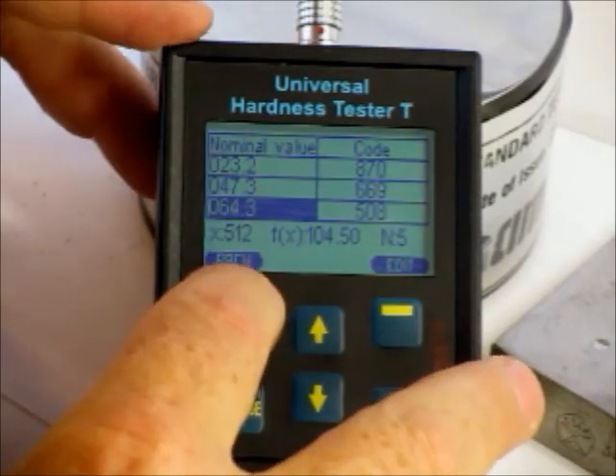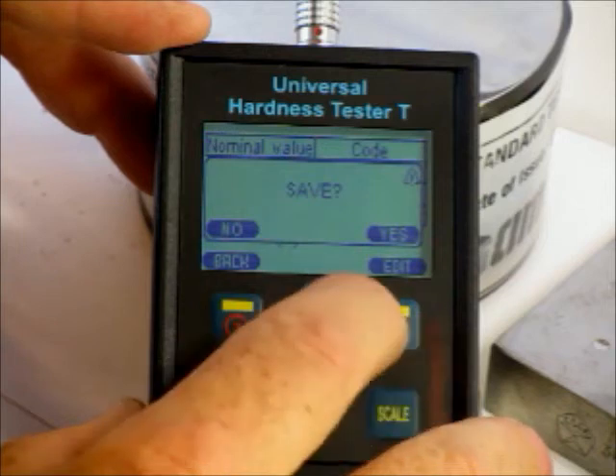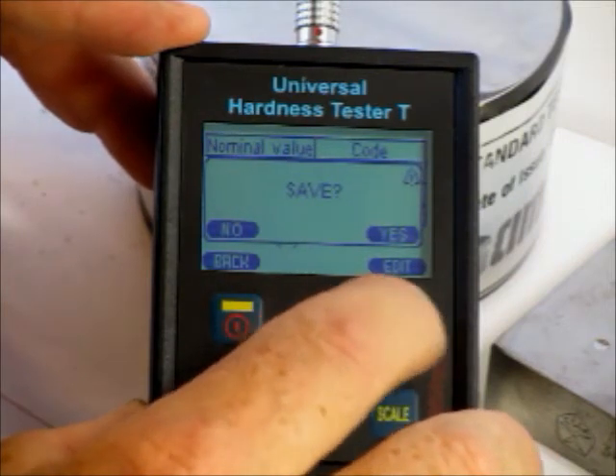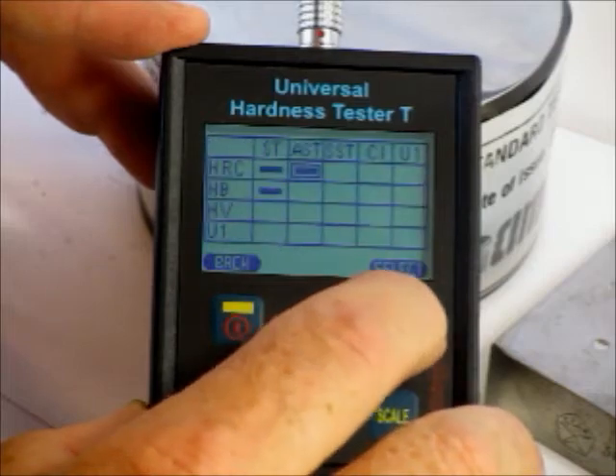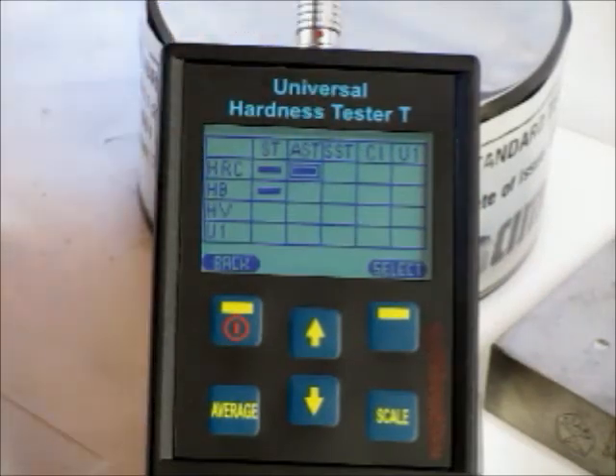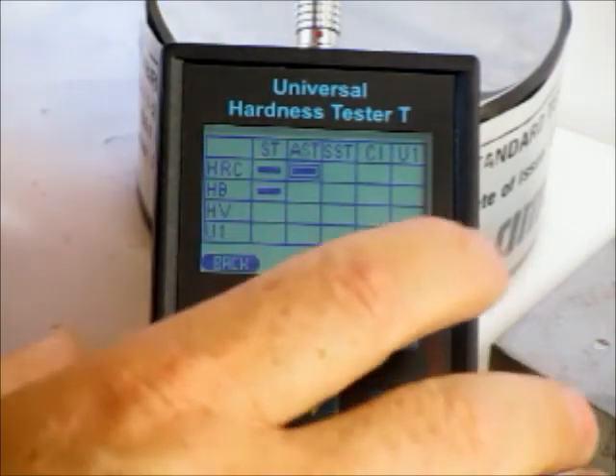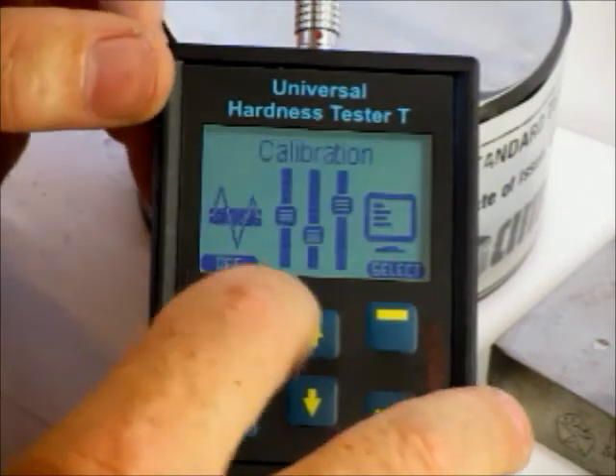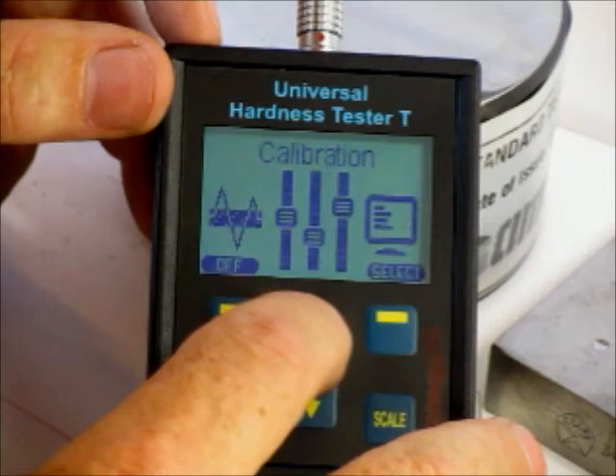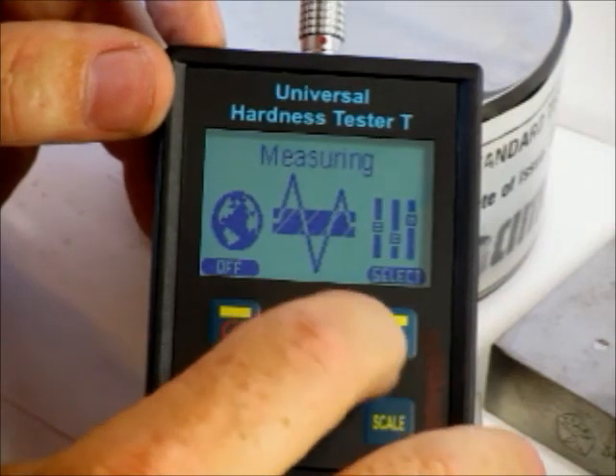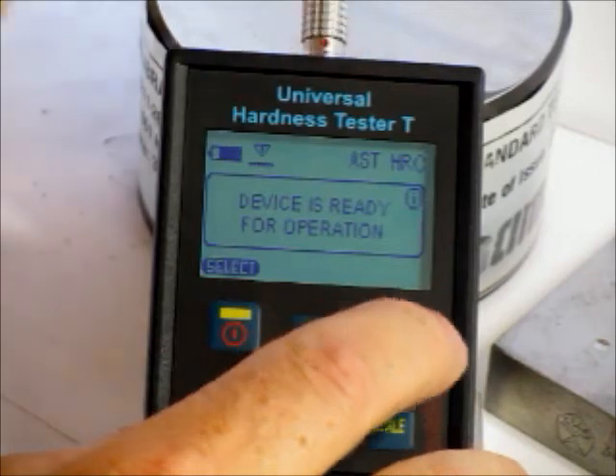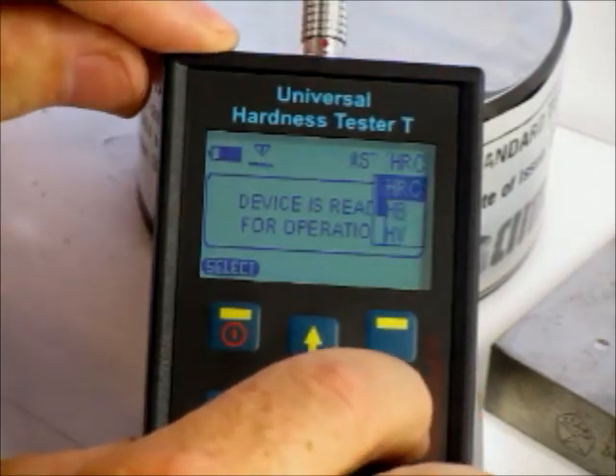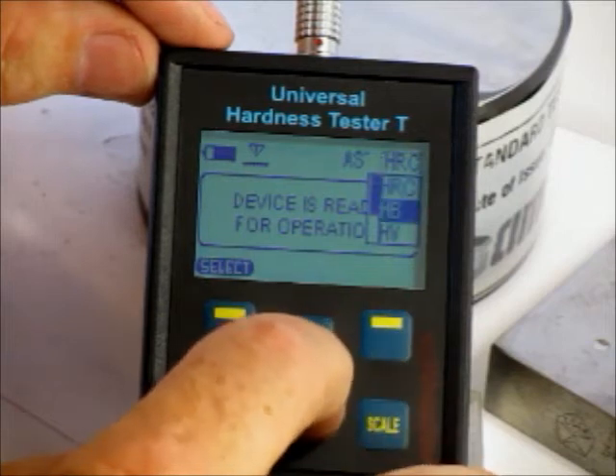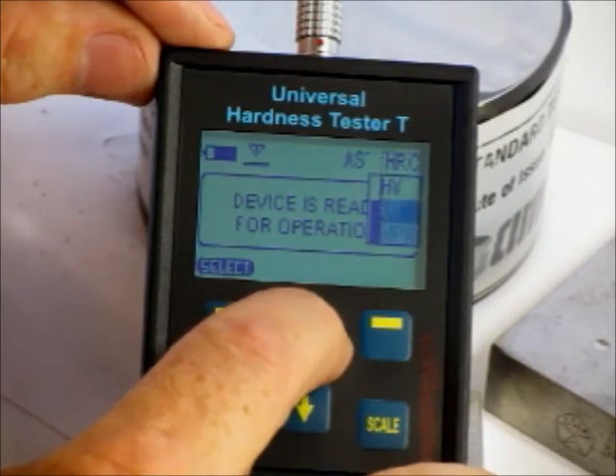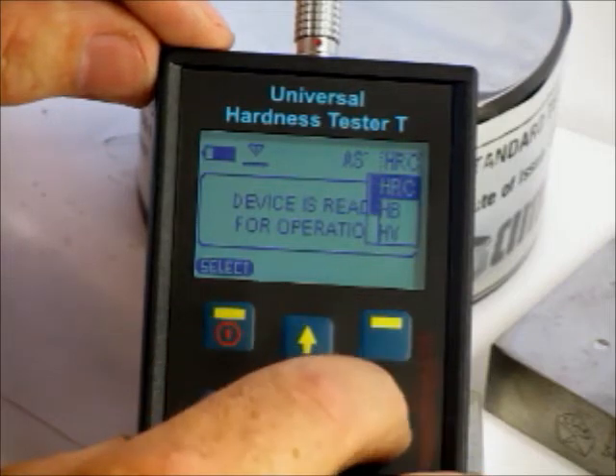We just hit the back button right now. It says, do I want to save my new calibration? I say yes. And there it is saved, and you can see here that now I have a little rectangle showing under Rockwell C that I've created for calibration. So now I can go back to my main screen, and what I have to make sure of is that when I'm doing my test, under measuring here, if I hit select, AST is shown and I'm in Rockwell C. I can change that scale to other scale types here. Alright, but of course I'd have to have those calibrated as well. Let's go back to HRC, set that.